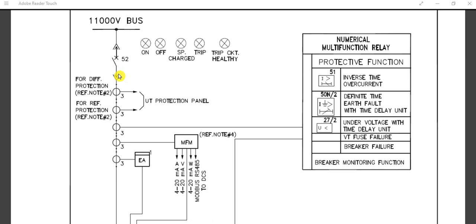On this 11kV bus, one circuit breaker is connected. The designation 52 represents the circuit breaker. This arrow mark symbol indicates that this is a draw-type circuit breaker — meaning it is a withdrawable breaker. There are LED indicating lamps on the breaker showing breaker status: breaker on, breaker off, and spring charged.